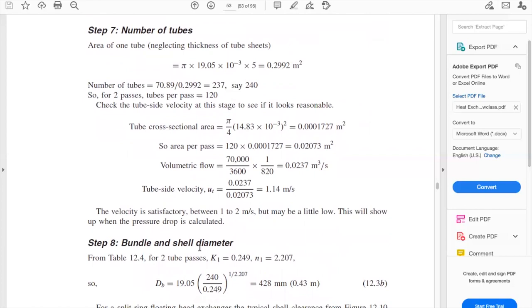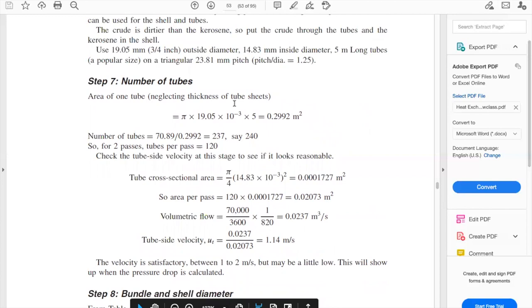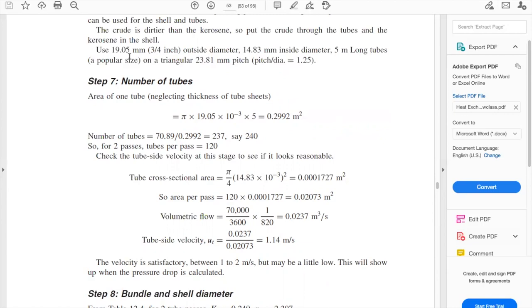Step seven: the number of tubes. First we need the area of one tube, neglecting the thickness of the tube sheets, because we assume they are so thin we can neglect them. We do pi times the outside diameter times the length of the tube. The outside diameter is 19.05 mm converted to meters (×10⁻³), and the tube length L is 5 meters. That gives an area of 0.2992 m² per tube.